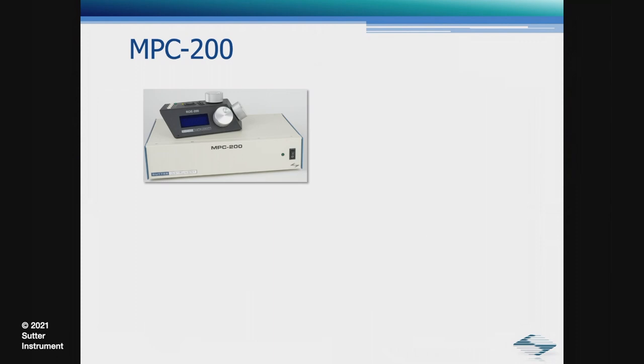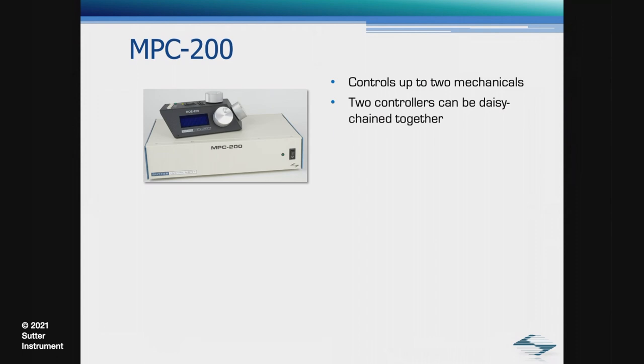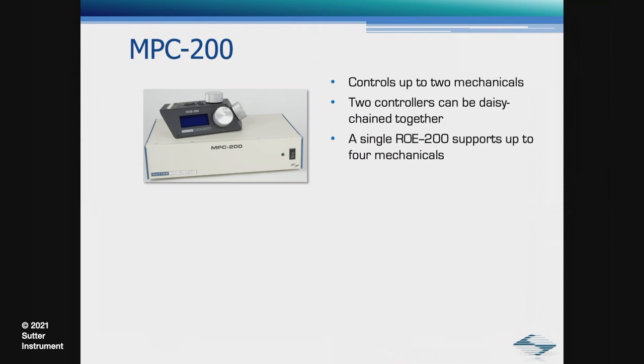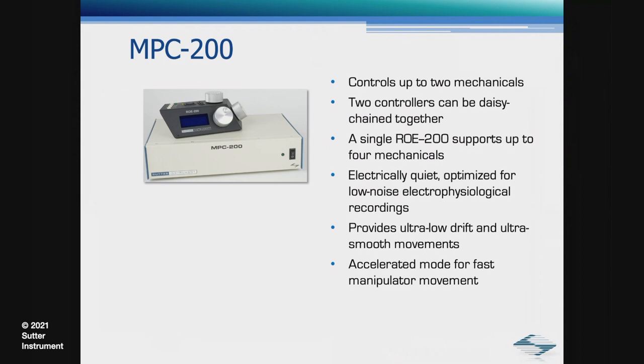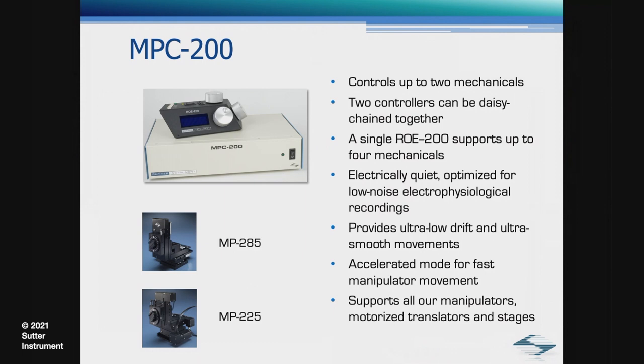First, the MPC 200 controllers. The MPC 200 controls up to two mechanicals. Two controllers can be daisy-chained together. A single ROE 200 supports up to four mechanicals. The controller is electrically quiet as it was optimized for low noise electrophysiological recordings. Provides ultra-low drift and ultra-smooth movements, has an accelerated mode for fast manipulator movement, and supports a variety of manipulator mechanicals, motorized translators, and motorized stages. The MPC 200 is also multi-link software compatible.